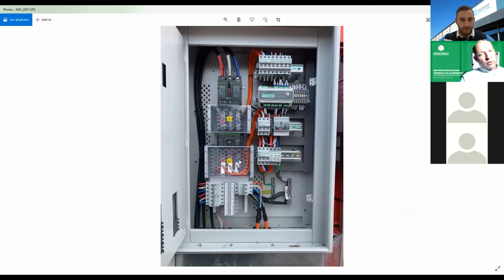Here's your relay. In case it shuts down, your Mains Pro detects that, activates and disengages the relay, and that shuts down all the solar inverters. The voltage sensing happens before the relay, so after a while, when the grid comes back into normal parameters, Mains Pro detects that it's safe, energizes again, and puts power back onto your solar inverters, which then start their normal 60 second re-engagement with everything.